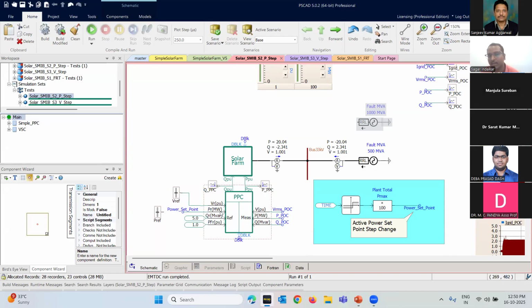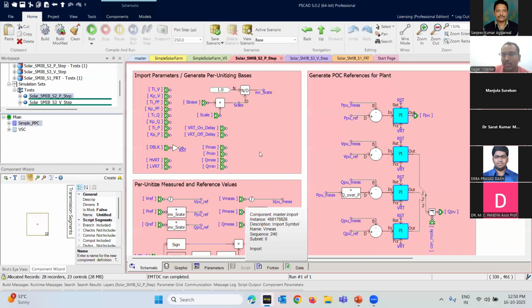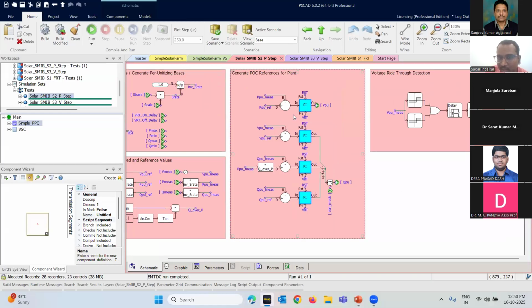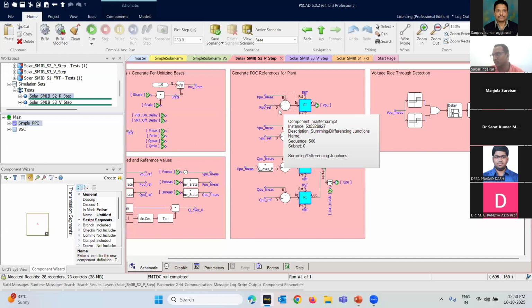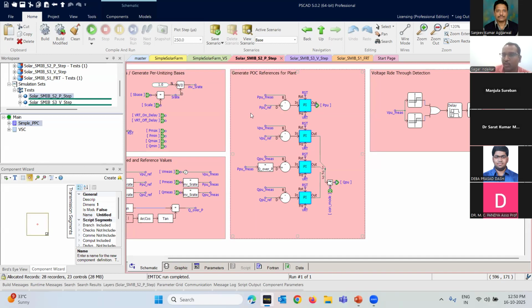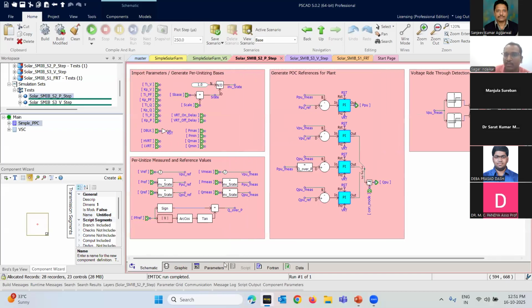And these references are the set points at which the plant should operate. And on the right, what you have are the measurements. So V RMS POI is the voltage at the POI, then active power at the POI, and reactive power at the POI. So based on the measurements and set points, the PPC will take certain decisions. If I go inside this box, you'll see a typical PPC. It's a very crude form of PPC, very simple. It does not have any modern function. It can only perform active power control, reactive power control, and voltage control. It doesn't have frequency support or a ramp rate limiter. It doesn't have any other important function that a typical PPC requires. But this does the work to demonstrate how the controls inside the PPC look. It's a much more involved control than what we have here.